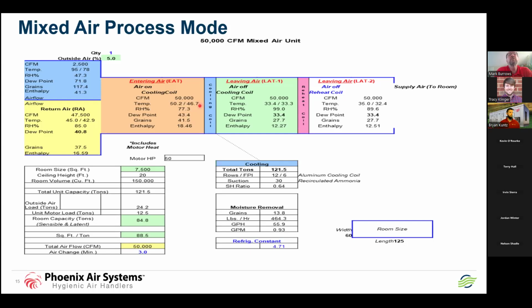Here's the air off the cooling coil. At a plus 30 suction, this is probably as good as it gets if we want to have a wet coil and not go through defrost. We're leaving at 33.4 dry bulb, 33.3 wet bulb. Is that pretty moist air? Yep, it's 99.0% relative humidity. We are certainly not going to absorb any moisture in the room with this airstream.